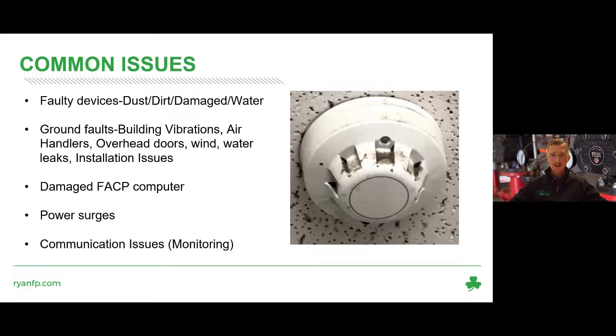So how do we handle or address a ground fault when it happens? How do we troubleshoot this issue? Basically we have to test each circuit to find the fault, and there are various ways to do this. We'll start at the panel, and once we determine what circuit the fault is on, we'll begin breaking down that circuit and splitting it to find exactly where that ground fault is located.